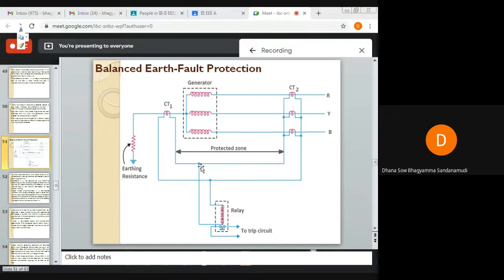This protection can only be used for protecting the alternator from earth faults, but it cannot be used for protection against phase-to-phase faults, unless these phase-to-phase faults develop into earth faults. So this balanced earth fault protection scheme can provide protection to the alternator windings only during an earth fault condition, if an LG fault occurs. If a phase-to-phase fault occurs, this scheme cannot provide protection against it. But if these phase-to-phase faults develop into earth faults, then those faults can be interrupted by this balanced earth fault protection scheme.